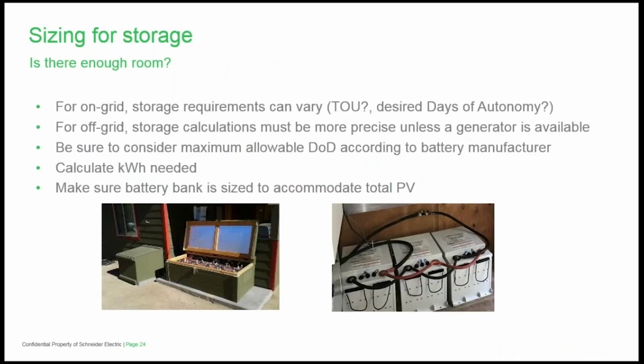So when we're sizing for the storage for on-grid, the requirements can really vary. Are they on time of use or not? Do they desire a certain number of days of backup or days of autonomy? Or are they just concerned with using stored energy to lower their electric bill? For off-grid, you're going to likely need to be more precise in your calculations unless you have a backup generator. If you do have a backup generator, then if you undersize the system, the downside is that the generator will start more often, but it's not the end of the world. If you don't have a generator for backup, then you really need to be accurate in your load assessment as well as your energy assessment so you can properly size the system.